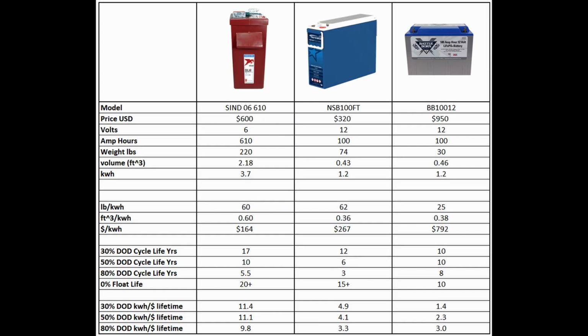Again, the 80% number is just there to throw the lithium battery a bone because it isn't useful, but the numbers are clear. Flooded lead acid wins, with AGM a clear second, and lithium lags behind. The 30% number is probably the most useful number for most applications, and here we see 11.4 kilowatt hours per dollar for flooded, 4.9 for AGM, and only 1.4 for lithium. This means that the lead acid batteries are significantly less expensive per amount of work that they do over their entire life. You don't save money by going to a lithium battery, at least not from these numbers. We'll do a more detailed analysis later and see if that changes.